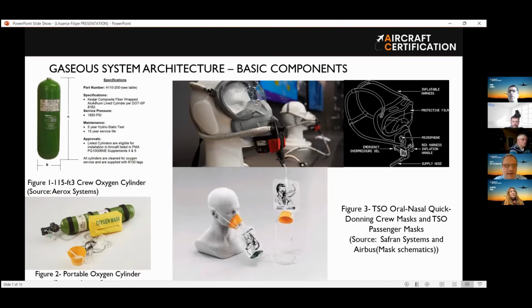So the Kevlar is far lighter. Right now the Kevlar has been added. The metallic, most of them, doesn't have hydrostatic testing. The Kevlar needs to have a hydrostatic test. It used to be 3 years, now it's 5 years. So every 5 years we remove the cylinder and do a hydrostatic test, which the supplier does, to make sure that the elastic properties are still part of the cylinder. And as I said, it's every 5 years, and every 15 years you have to remove and change the cylinder.